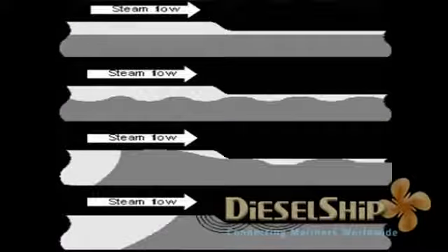And this picture which is over here shows the steam which is creating a water hammer in a pipeline which already has lots of water, for example, boiler feed water line. So the water is filled up over here, and as the steam flows, it creates ripples, and thus these ripples form as big water waves and hit the pipeline, creating water hammer. And this happens on boiler feed lines and some freshwater lines, for example hot water circulating line, etc., if it's getting overheated more than 100 degrees.